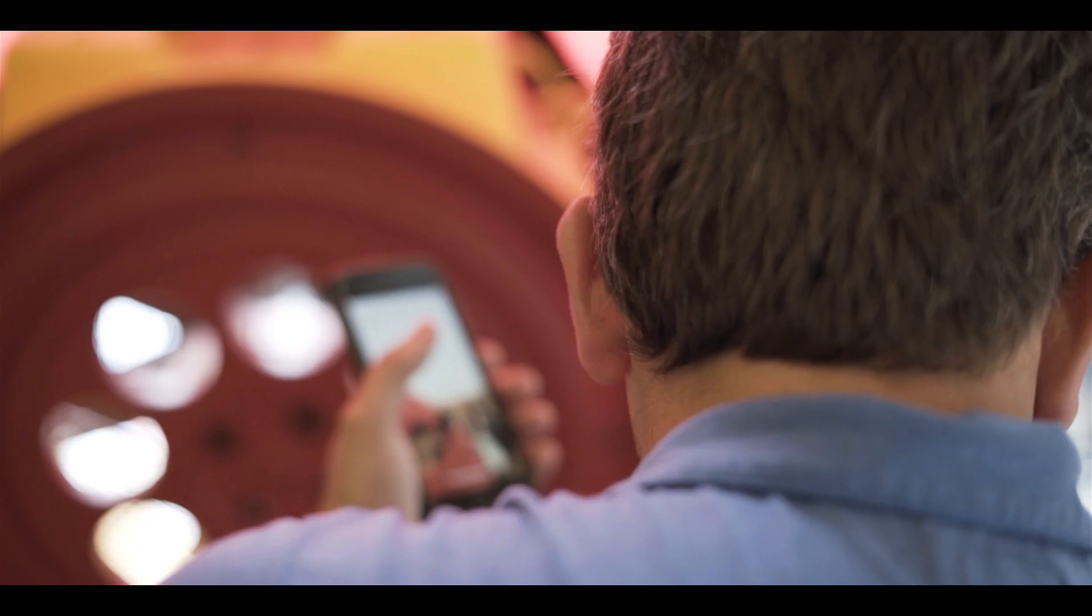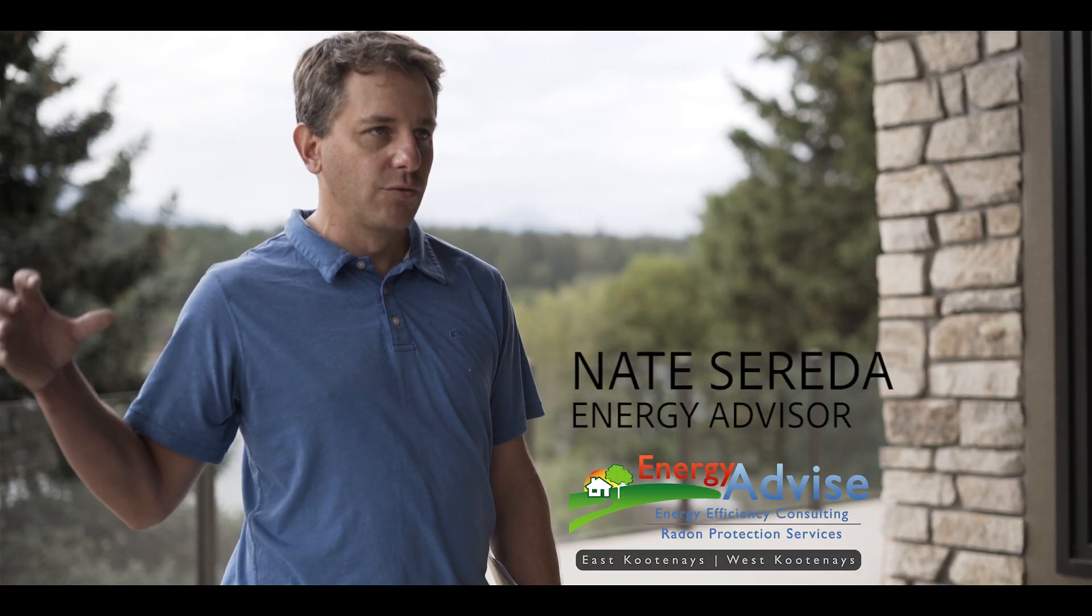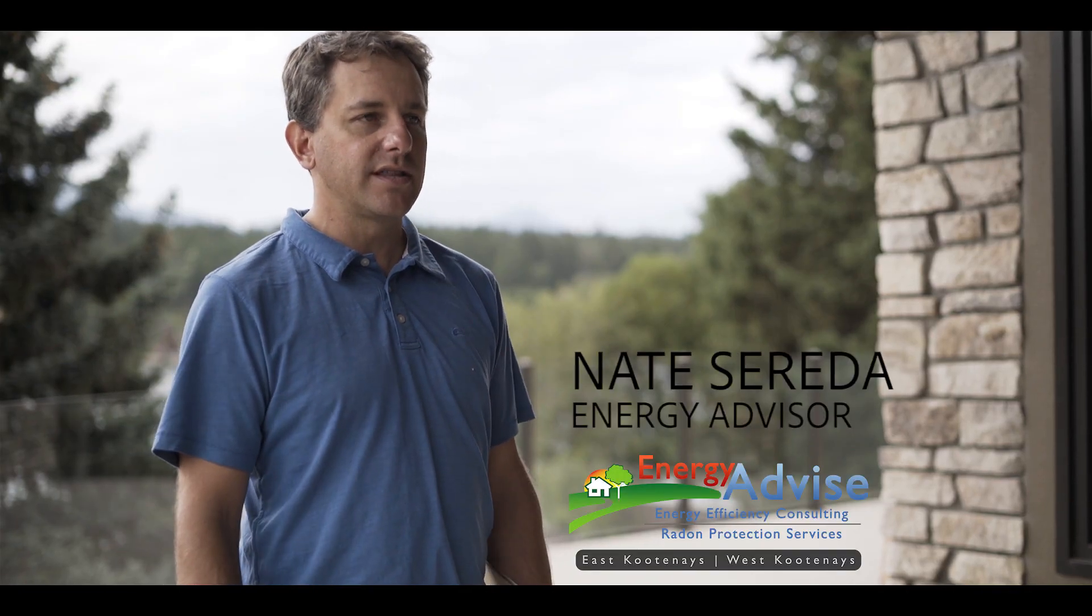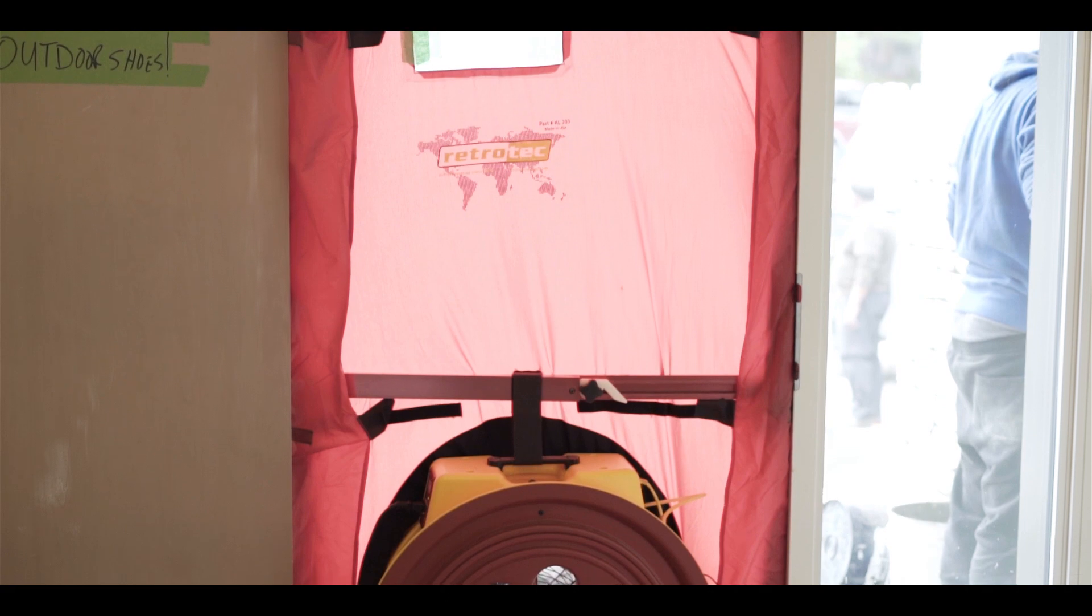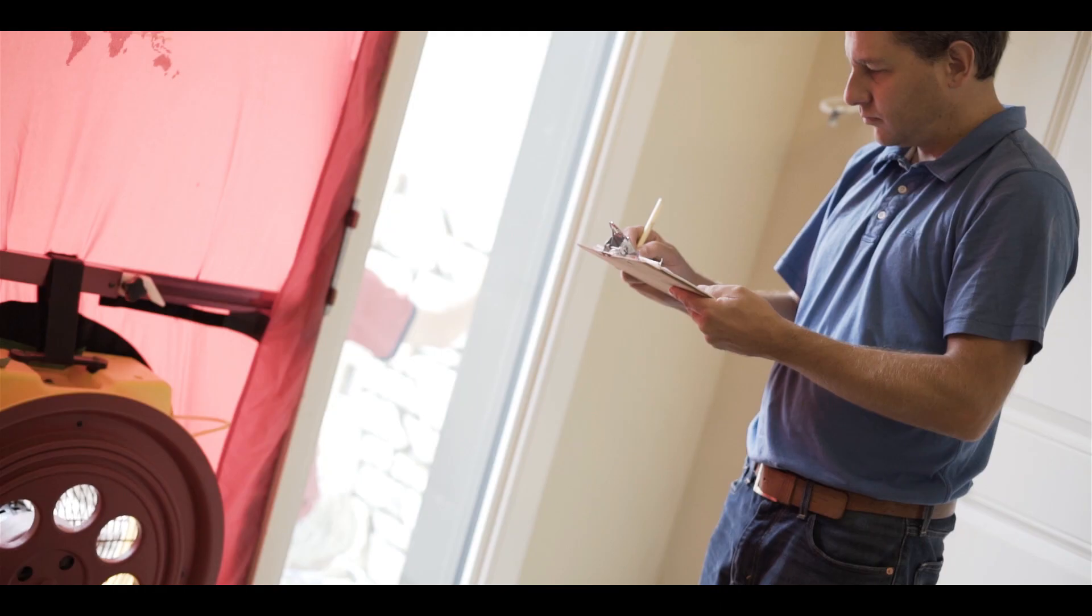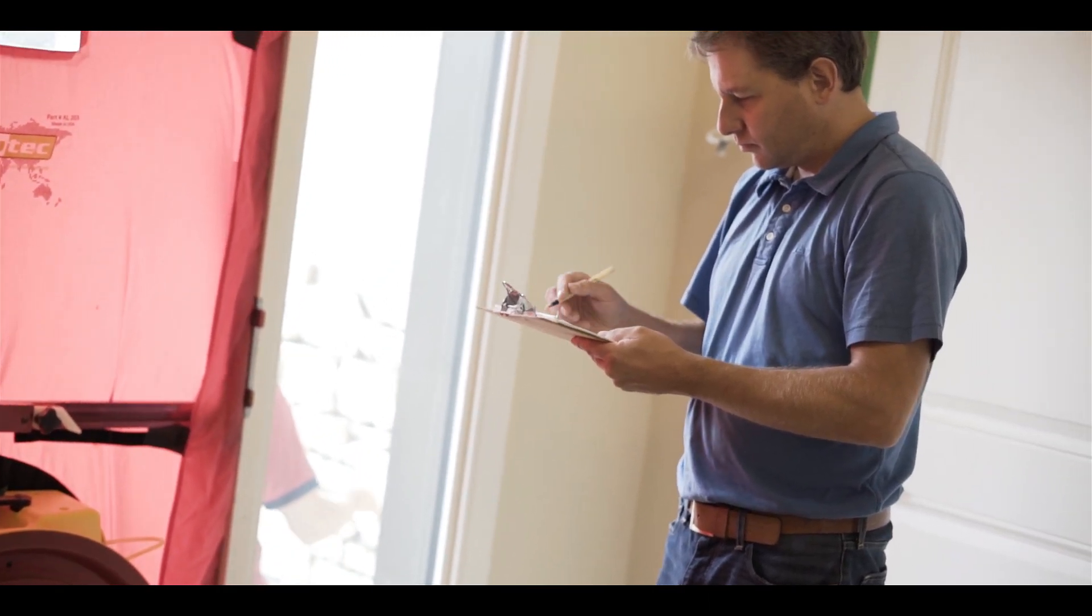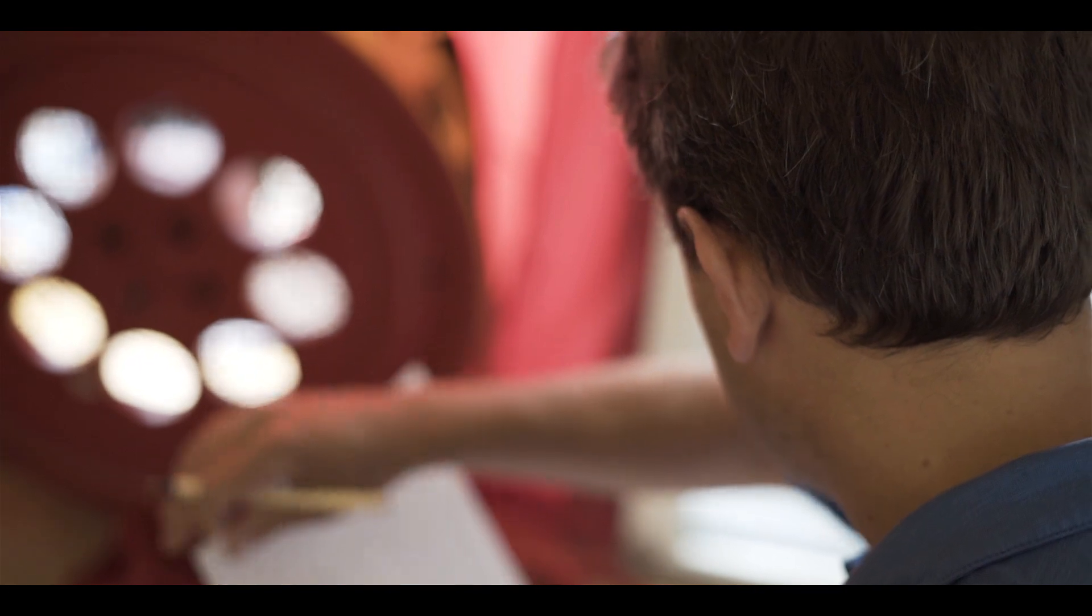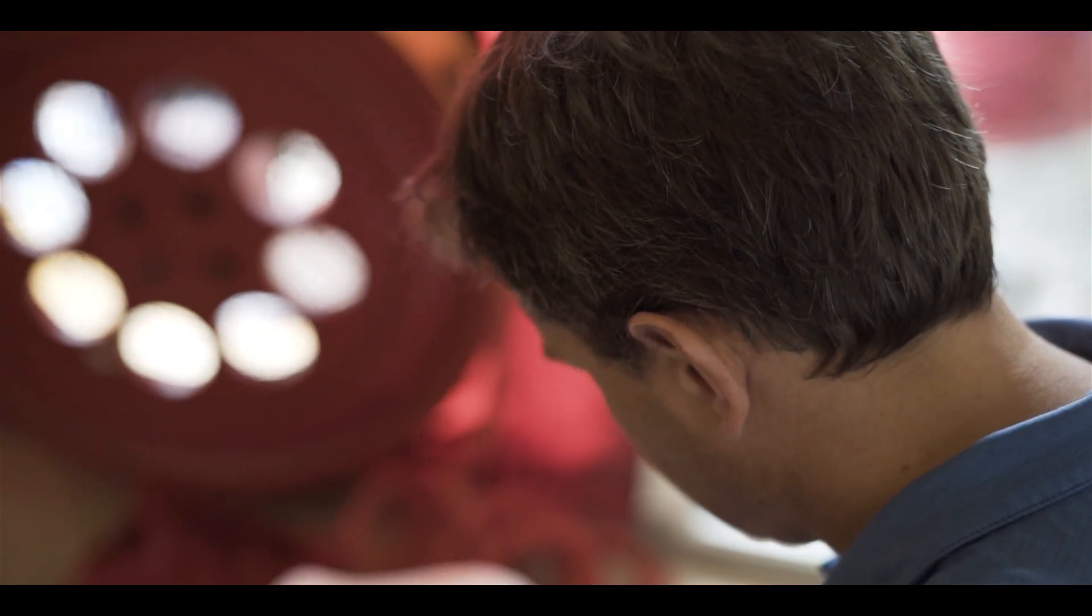What that means is with a depressurization test, I suck air through the house. I close up all the windows and then we measure unwanted air leakage through the building envelope. If we minimize that air leakage, we can save money from an energy standpoint, but it also helps control moisture entry into the walls, which can eventually, if really bad, develop mold and other issues.